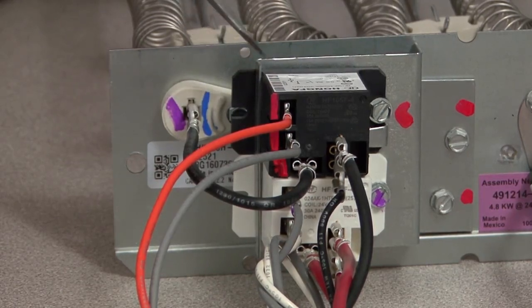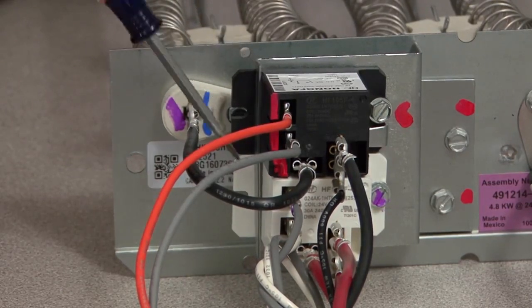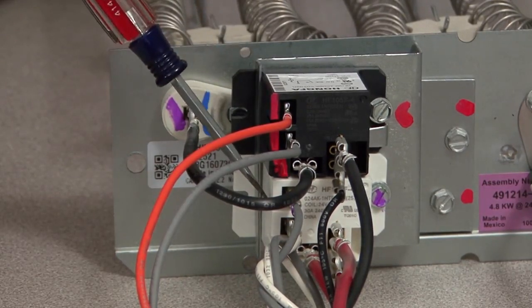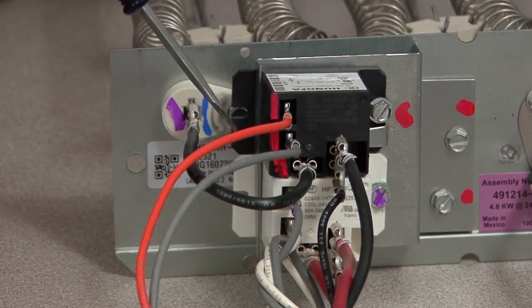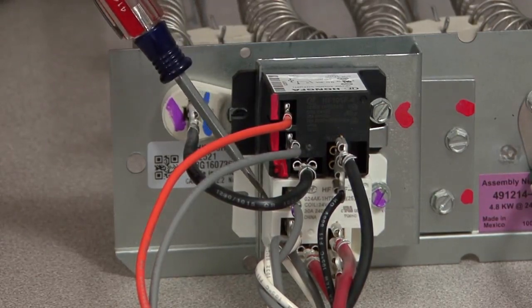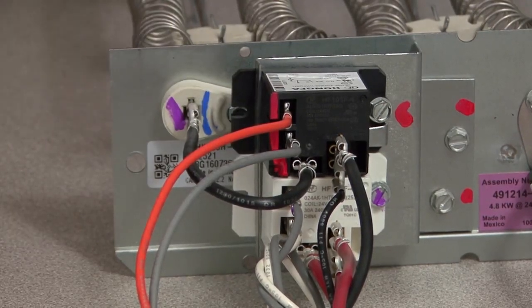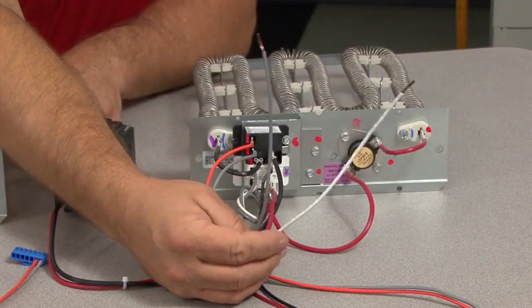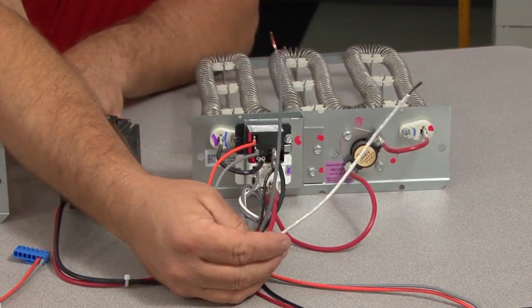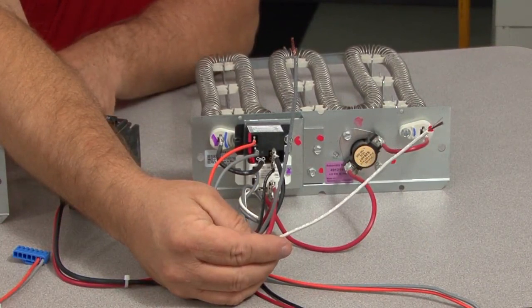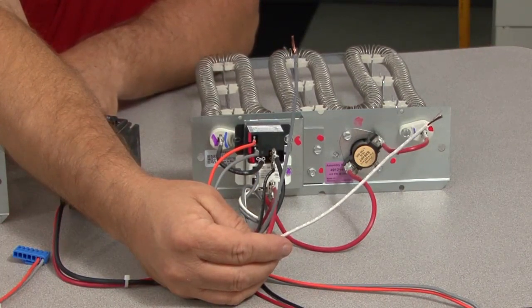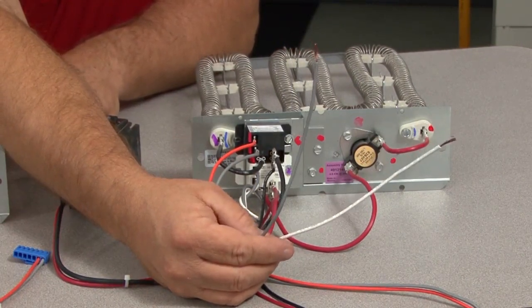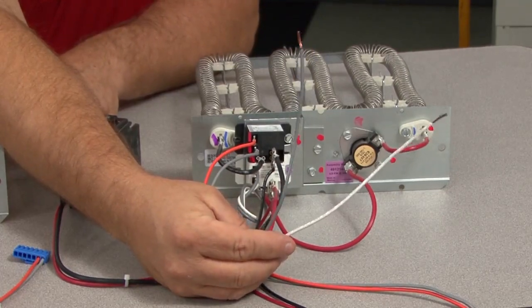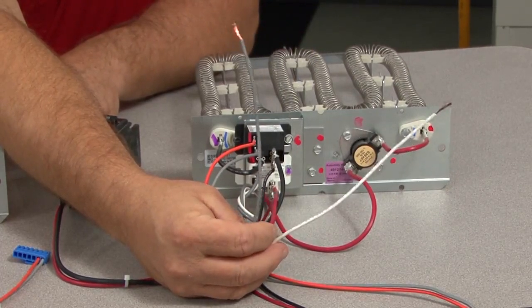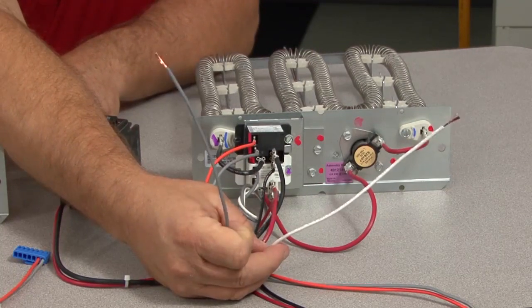Okay? Just remember, the black relays are always going to be DC control relays, and the white relays are always going to be AC control relays. And in order to get those AC control relays powered up, we're going to need the white and gray wire coming from the heater kit to W and C. And if you had a 2-stage air handler control board, it would be W1 and C. So that when you get a call for heat, W1 gets energized on the white wire, C being hot all the time.